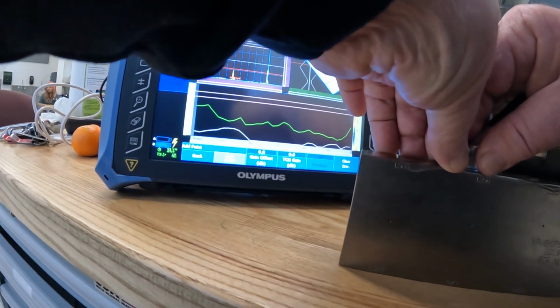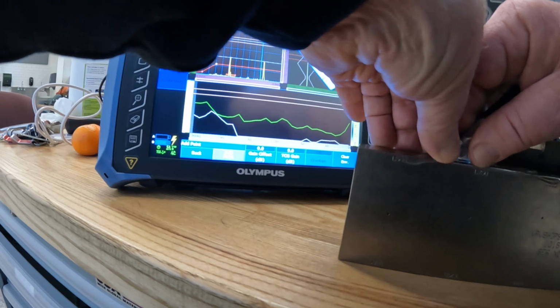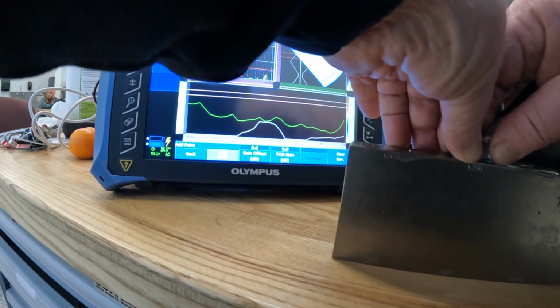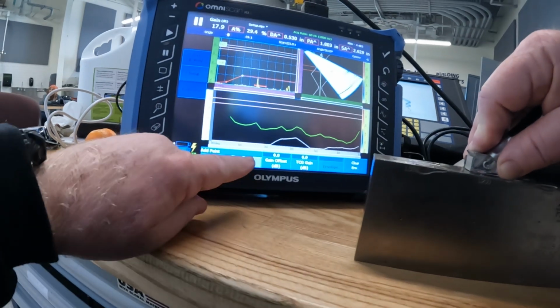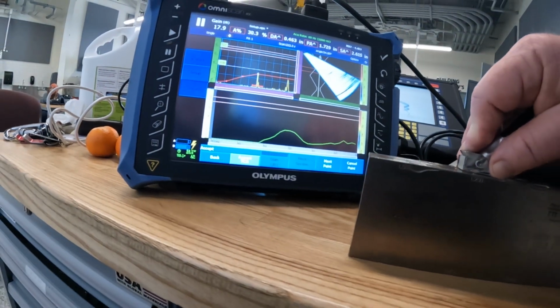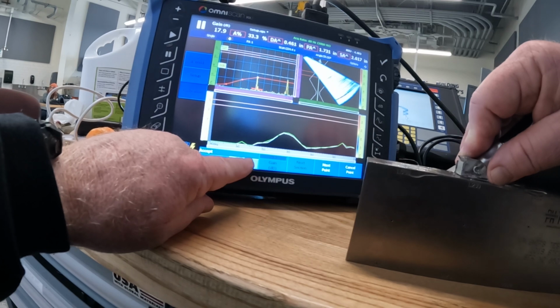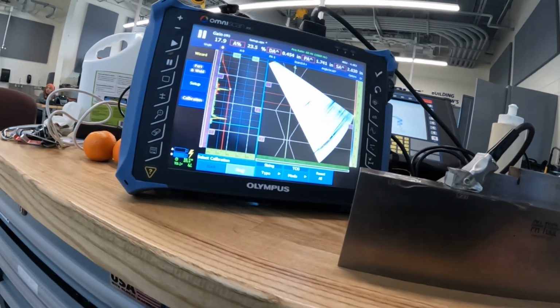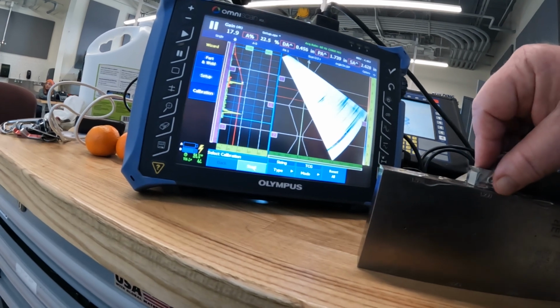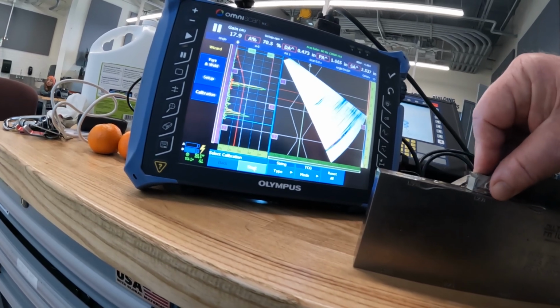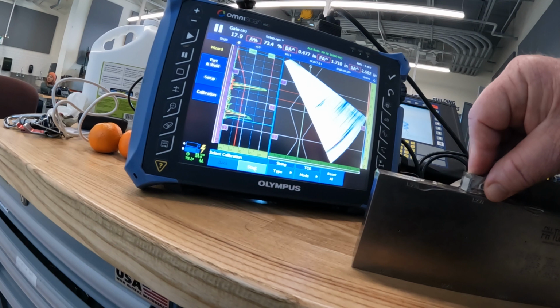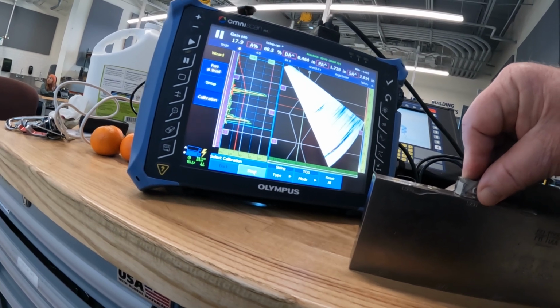I want to make sure that I'm pressing hard enough. So I want to make sure I've got adequate gain. I'd prefer to have a smooth curve all the way across. One like this one is probably not optimal. So I've completed that. Now I've got 3 points. I'm going to hit accept. And so it's basically turned on the TGC, which, what does that mean? That means when I go over the reflector, it's going to carry me up to the reference level. You see that?